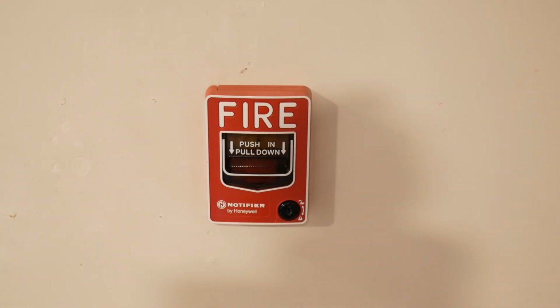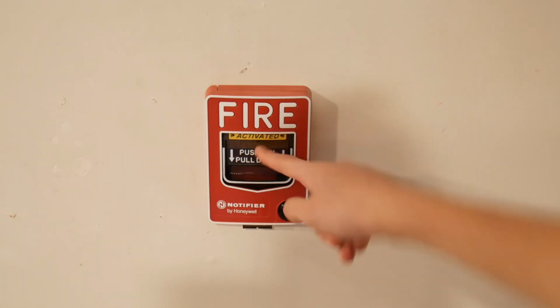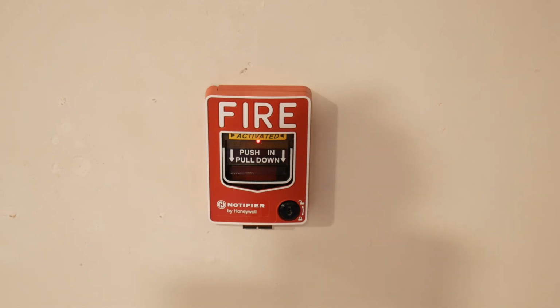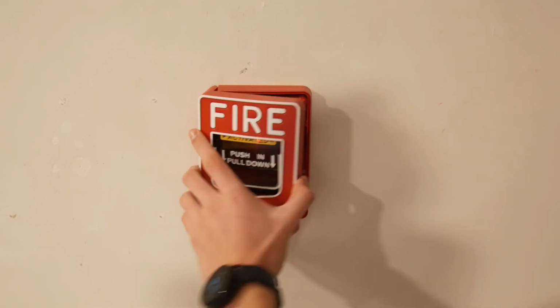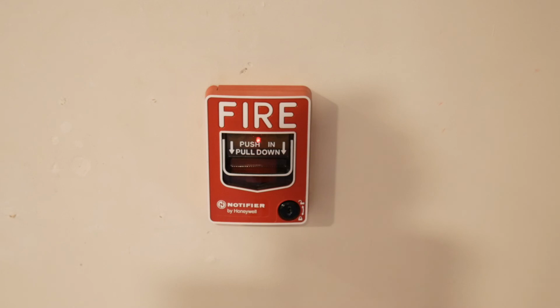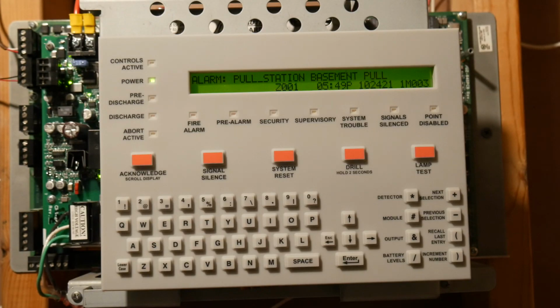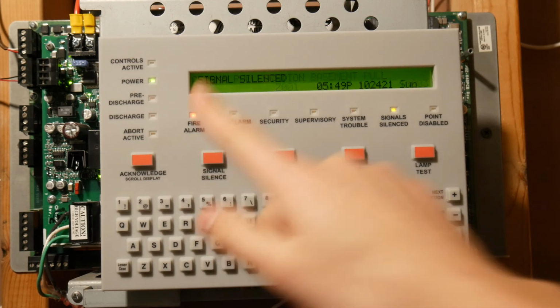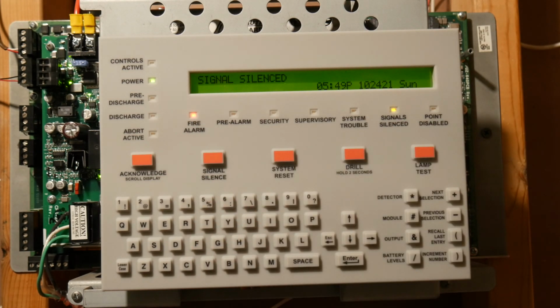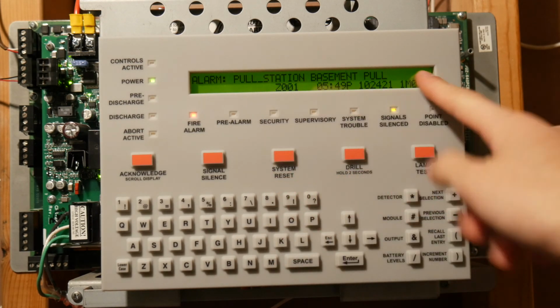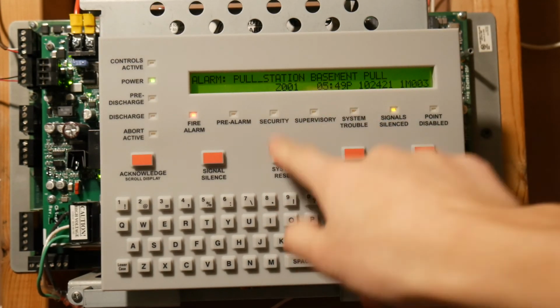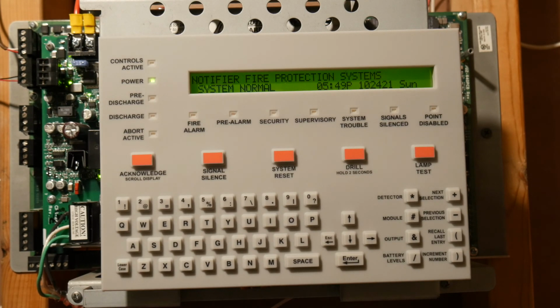So I'll pull it. So we're gonna push in, pull down. And I'll cut to the panel. Okay, so as you can see, we successfully programmed that NAC because it's saying pull station, basement, pull zone 1. So we successfully programmed that, and as you can see, it was still blinking. So we programmed selectable silence as well.